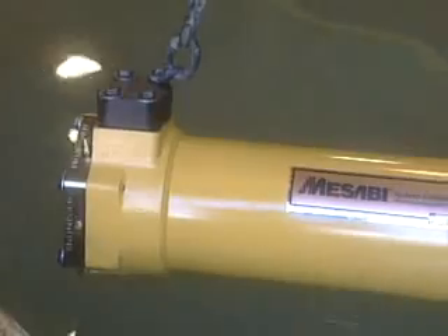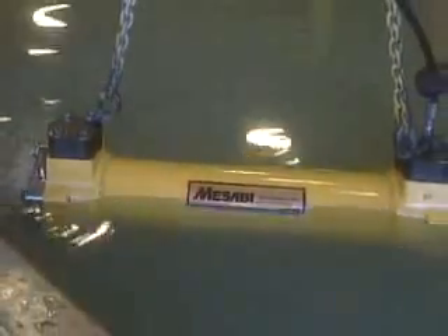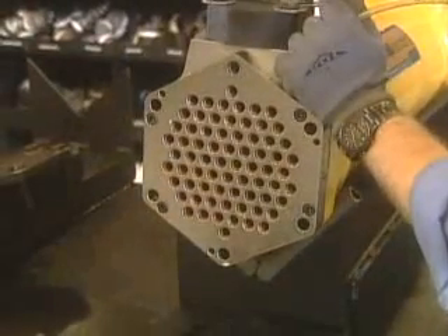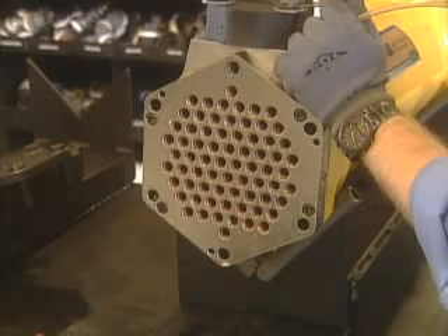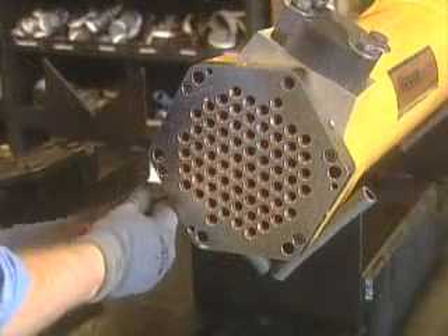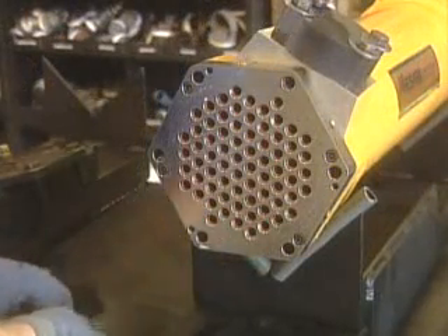Check for leaks at the detection ports and tube ends. If a leak is detected, repair as required. After any repair, restart the test at step 1. Continue until the cycle sequence is completed. After each test sequence, dry the detection chamber with compressed air. Remove the opposite detection port plug to aid in drying.